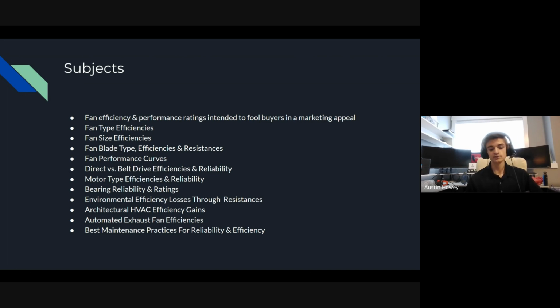If you have a fan, this is actually the most common problem I see: people buy fans and they last about 6 months to 18 months, or they might get lucky and get 2 years out of their fans. But in the process of that, you're doing a 2-year ROI, and those fans over time are losing their efficiency. If your fan is dying in 2 years, that means that progressively every year you're losing half of the efficiency of your fan, because your bearings are essentially grinding.